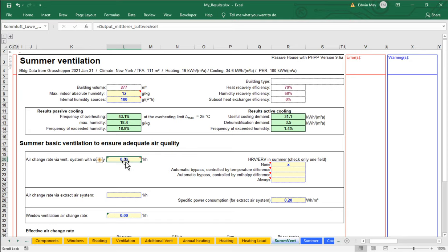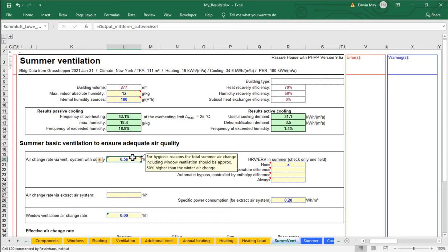However, if I hover over this cell for a second, notice that we get a little warning here from PHI. They say, for hygienic reasons, the total summer air change, including window ventilation, should be approximately 50% higher than your winter air change rate. So if my winter air change rate is 0.56, then my total summertime air change rate should be 50% higher than that, so around 0.8 or so.